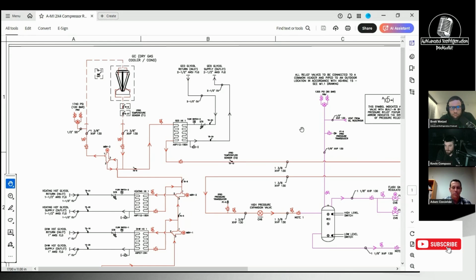You don't have a very large temperature difference. Your coil defrosts at 32 degrees. So you want your defrost temperature to be much greater than 32 degrees so you can condense. So you can put a regulator upstream of the receiver to increase the defrost pressure/temperature, and you can defrost much faster. But with supermarket systems limited to 650 psi, you just don't get that capability to raise that pressure up too much without the risk of a valve hanging up a little bit or blowing the CO2 charge because you build up the pressure too much in the receiver.